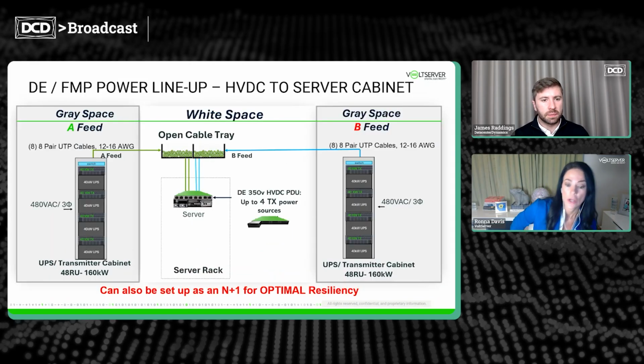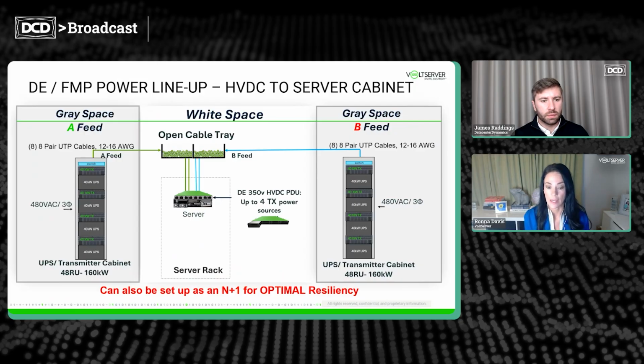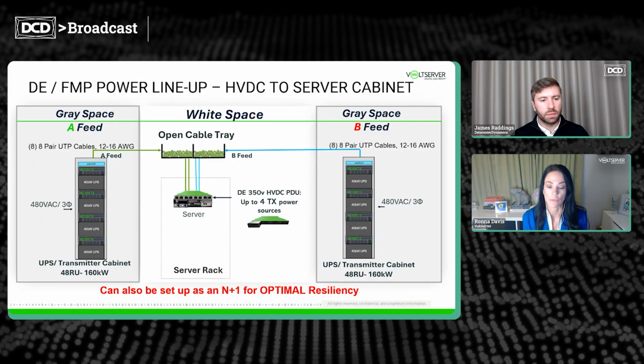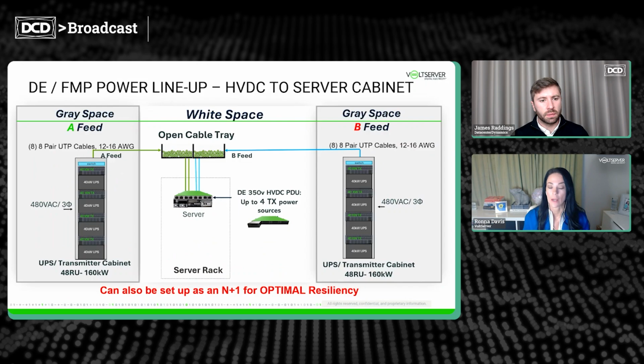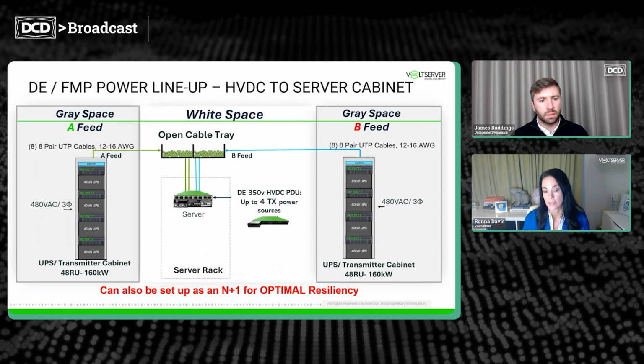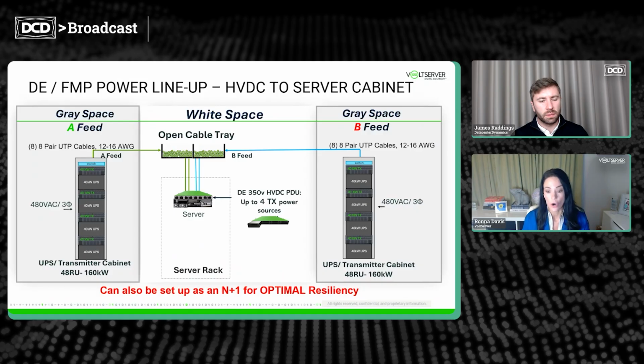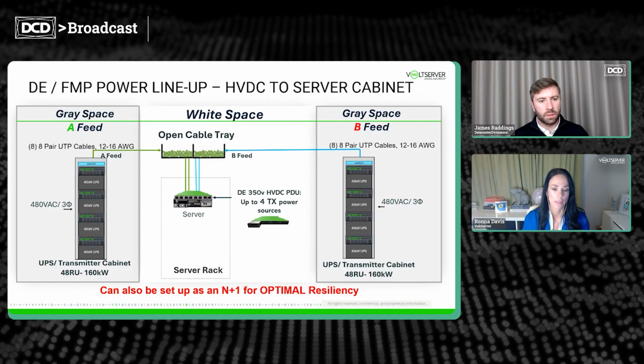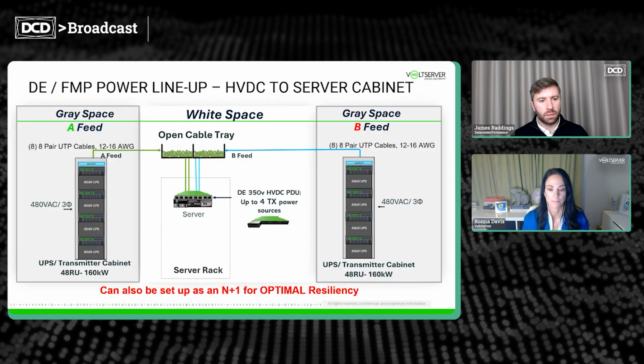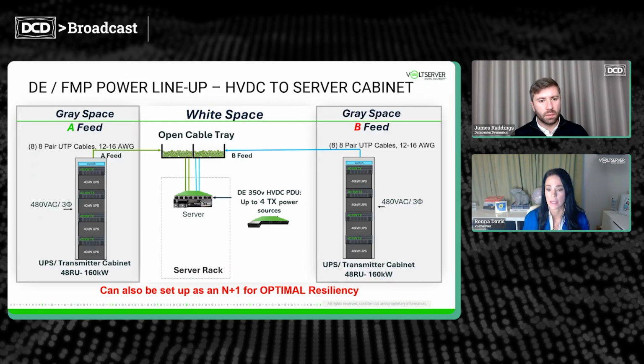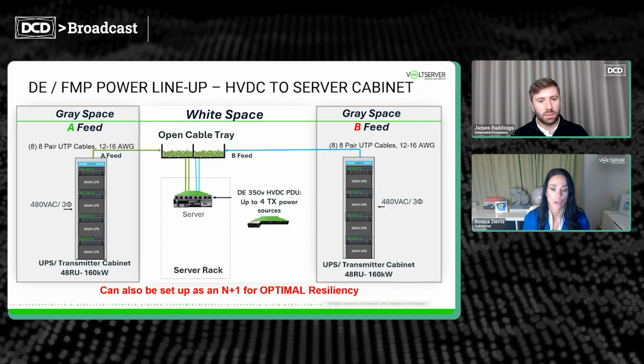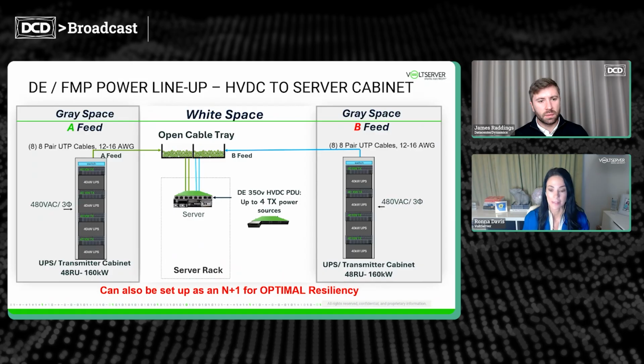In your gray space, you have your power entrance facility that feeds your UPS transmitter rack. Now, in this case, we're showing 160 kilowatt UPS and 160 kilowatt transmitters, which for comparison, our transmitter would be like the floor PDU in a legacy AC system. From your 160 kilowatt UPS transmitter rack, we have 8 pair 12 to 16 gauge UTP cables in an open basket tray. So it's a pretty small cable bundle.